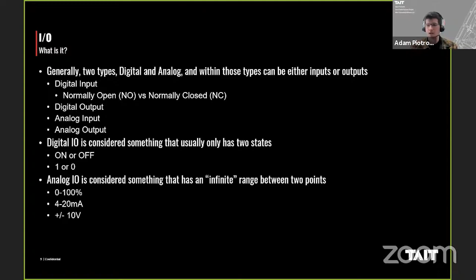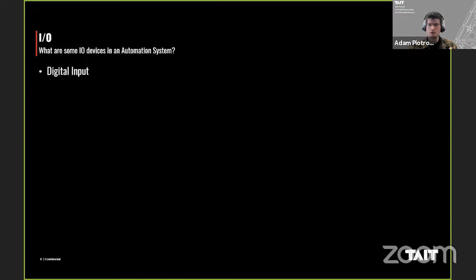So how do we then use this I/O in a system, and what do control system designers have to be aware of to make sure that they accommodate, be it the MCC or the MCR, when it comes to actually designing these cabinets and putting these systems together? So from a digital input standpoint, we have things like limits, brake check back, e-stop buttons, and your go and stop buttons. So limits, from the TAIT standpoint, our machines usually end up having 6 sets of limits, 3 on each side. The higher range and the lower range are a plus and minus direction. And one of those limits is purely software based. It lives in the controller, doesn't actually have any switches. So we don't have to worry about that from a digital input standpoint.